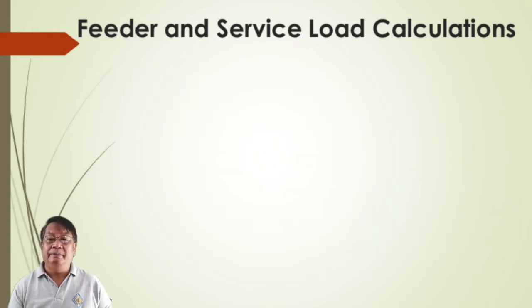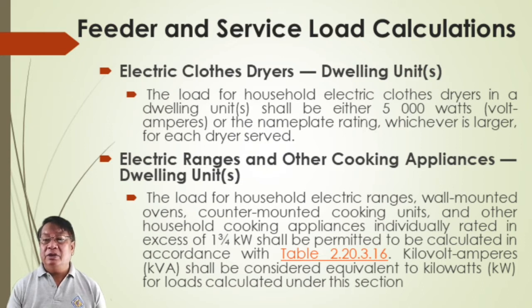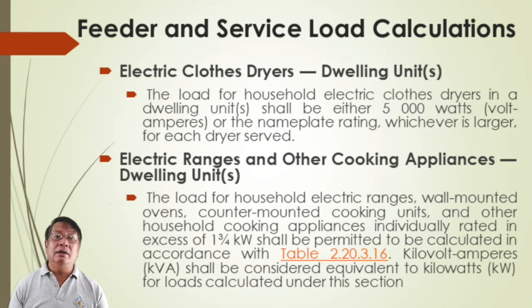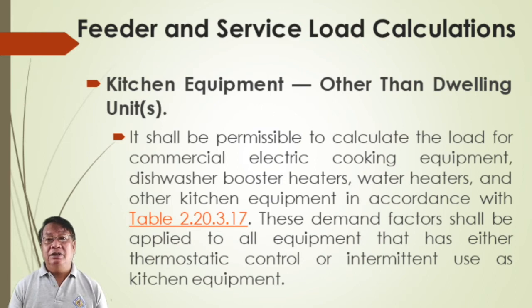For electric clothes dryers, to determine the feeder size, it shall be either 5,000 watts or the nameplate rating, whichever is larger, for each dryer served. If you know the actual load rating, try to use the actual load rating. The demand factor for kitchen heating appliances or specifically the electric range was shown previously.